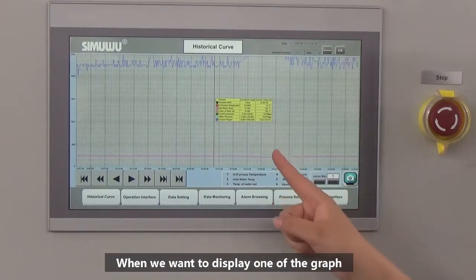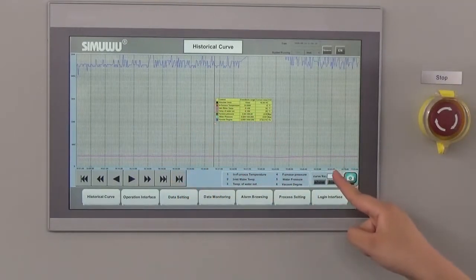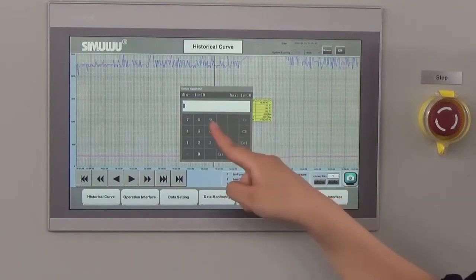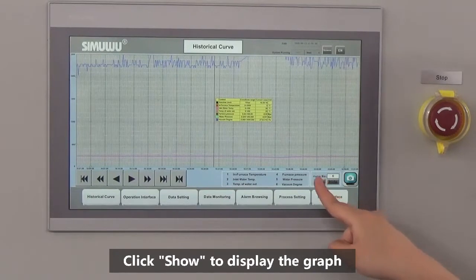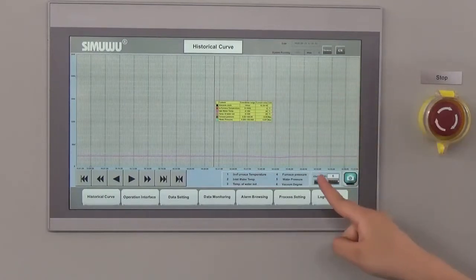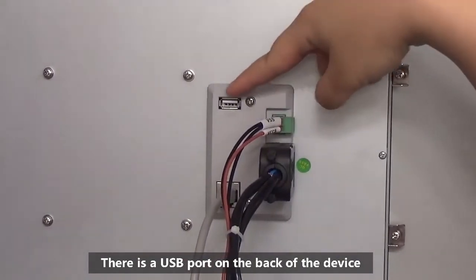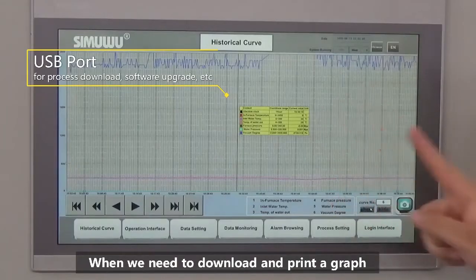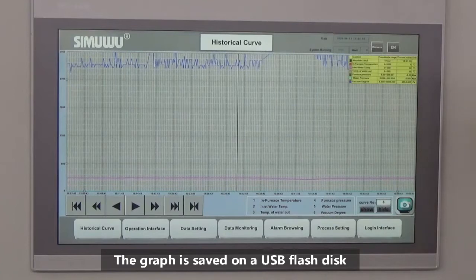When we want to display one of the graphs, we enter the corresponding graph number at this position. For example, for the vacuum degree graph, we choose number 6. Click OK, then click Show to display the graph, or click Hide to hide it. There is a USB port on the back of the device — you can plug in a USB flash drive. When you need to download and print a graph, click this button and the graph will be saved to the USB flash drive.